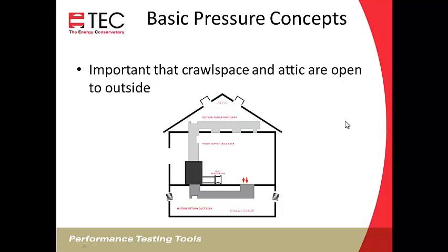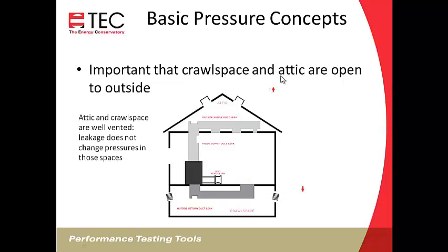It's also important that crawl spaces and attics are open to the outside, because we're going to be blowing air through those spaces. If they're well vented to the outside, we're not going to cause any pressure in the attic or the crawl space by that air moving through that space, because we've got air leaking from the ductwork to the attic and then from the attic to the outside. If the attic's well vented, it won't affect pressures in the attic. Same with the crawl space.